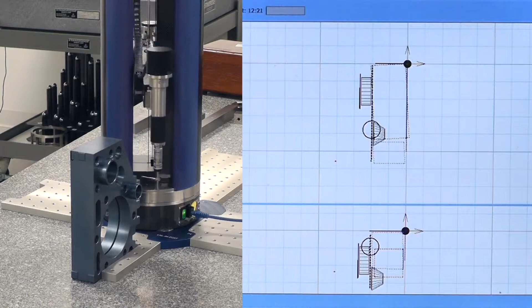You'll see that it switched to the horizontal probe on the screen. It also switched to horizontal probe 1, and now it's going to measure a lot of the same features using the horizontal probe. Now it's measuring a plane, because when we're using the zCAT or any other CMM, when you start measuring diameters and cones and lines, it likes to reference off of a plane. So the first thing I do a lot of times is measure a plane so I can reference off that. Here I actually measured another plane on the top of that cylinder, and now I told it to measure the outside diameter of that cylinder.